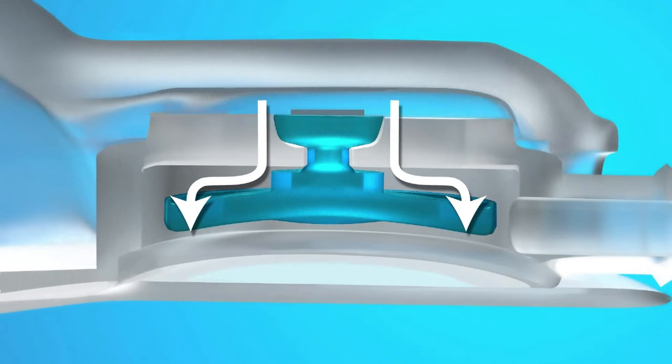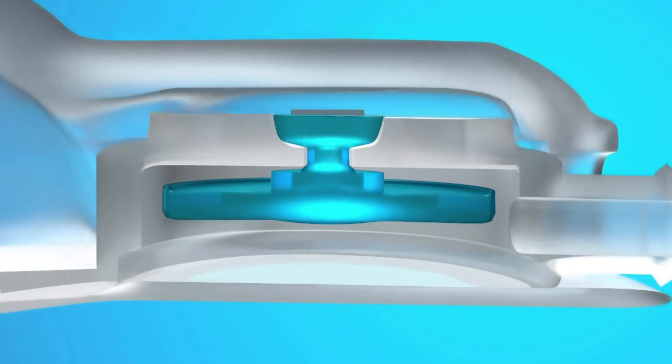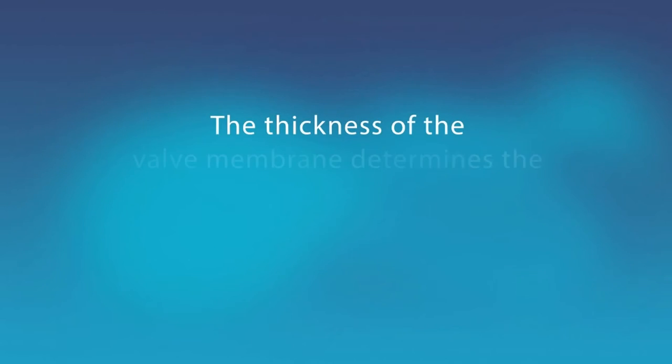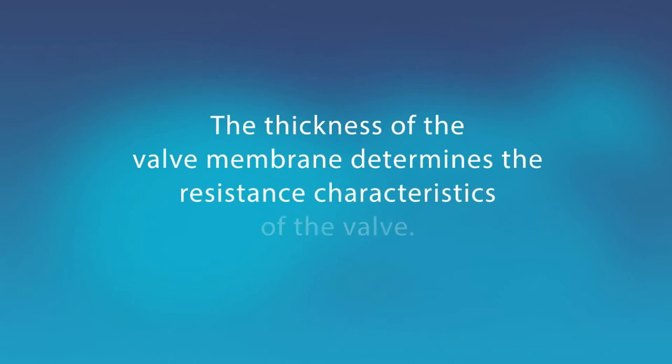When the ICP is lower than the resistance of the silicone umbrella, the mechanism closes. The thickness of the valve membrane determines the resistance characteristics of the valve. The thinner the membrane, the lower the valve resistance. The thicker the membrane, the higher the valve resistance.